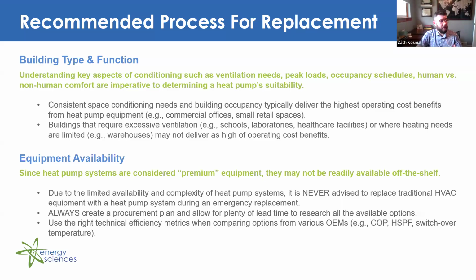And so we also have equipment availability. Since heat pump systems are considered premium equipment, they may not be readily available off the shelf. It is advised to never replace traditional HVAC equipment with a heat pump system during an emergency replacement. Always take that extra time to flush out all the details and have the right design intent before you're replacing a system with heat pumps.